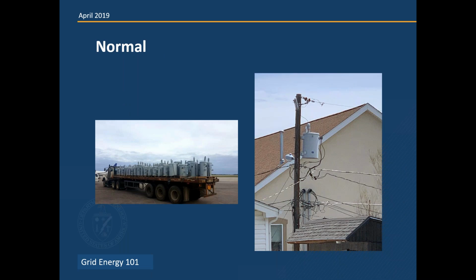So I got the same thing in this picture as the last slide. I have a bunch of transformers. On the truck there, that's a picture of some transformers over in Saipan when we responded last year to Hurricane or Typhoon Wutip and or Wutu. And then on the right, we have a typical pole-mounted transformer. And so it comes in single phase there, goes through the fuse and comes into that transformer. And on the right side of that can, the can is the transformer, there's insulated wires, service wires that go to the house. And you can see past that transformer is what they call a weatherhead. And that's where the overhead connection is made and goes into the customer's meter. Next slide, please.